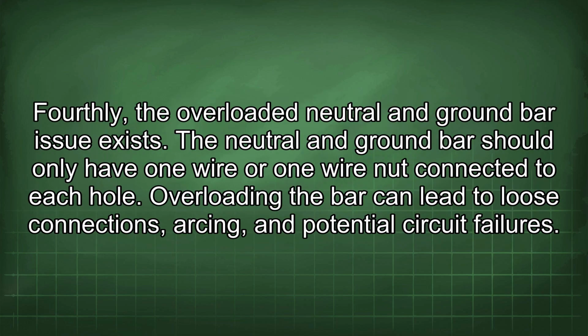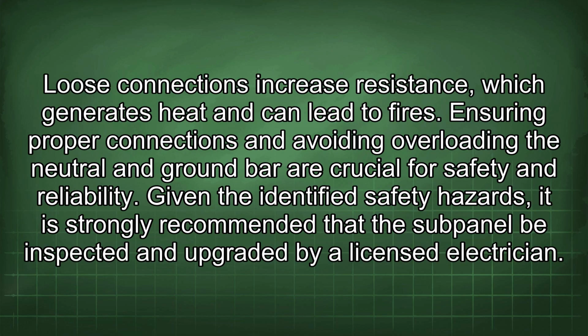Fourthly, the overloaded neutral and ground bar issue exists. The neutral and ground bar should only have one wire connected to each hole. Overloading the bar can lead to loose connections, arcing, and potential circuit failures. Loose connections increase resistance, which generates heat and can lead to fires. Ensuring proper connections and avoiding overloading the neutral and ground bar are crucial for safety and reliability.